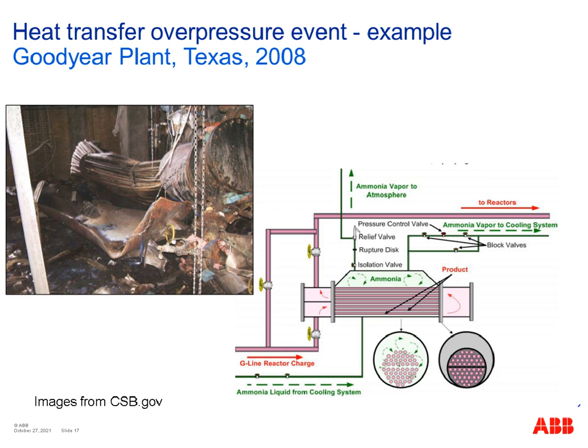And the process side of the exchanger was being subjected to steam cleaning. So there was steam in the tube side of the exchanger, and therefore there was energy going from that steam into the ammonia. The ammonia vapor that was caused by the boiling from the energy from that steam had nowhere to go. It was completely blocked in, and that resulted in overpressure of the ammonia side of the exchanger, and we had an explosion. And as I say, there was 1 fatality and 6 injuries there.